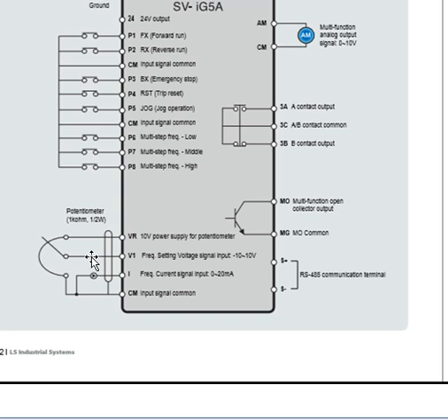And V1 is the variable input to the VFD that can be 0 to 10 volt or minus 10 to plus 10 volts. And the I terminal, you can give here a variable current on this terminal, and here the fourth terminal is a common terminal for the potentiometer.